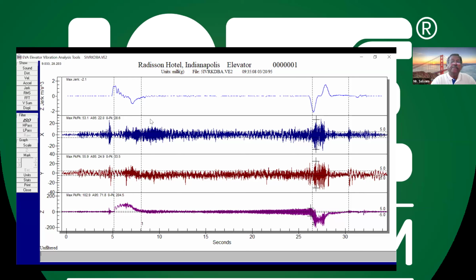But as per the standards, we are not interested in more than some frequency. I told you in the frequency graph, beyond 10 hertz the body response will be poor. Like when you want to solve a problem, the 80-20 principle: 80% of the time, what is there is maybe less than 10 hertz, which causes the high sensitivity of the body. So there is a filter. I told you, in the construction of the equipment there is a software filter which can filter out beyond 10 hertz. It's called the ISO filter, because as per the standard they ask to knock off the frequency beyond 10 hertz and see the performance. For R&D purposes, you can analyze using this graph.